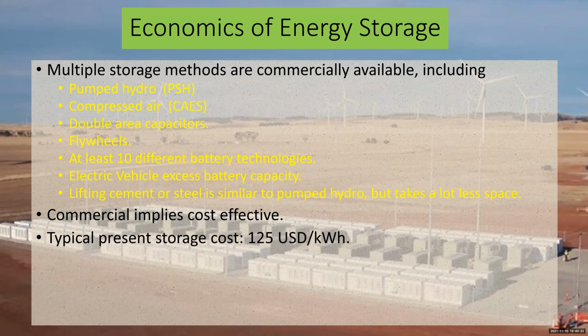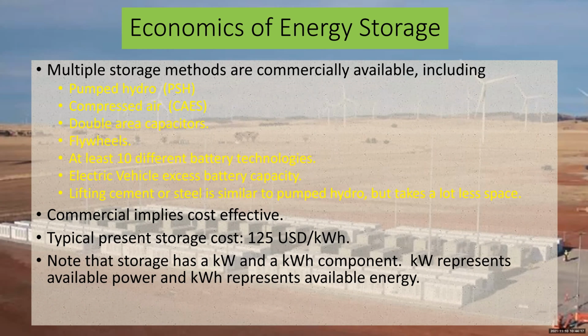Right now, storage is costing around $125 US per kilowatt hour. We learned from Orlando Utilities that this is for installation, but for every kilowatt hour you store, you can do that every day, in and out. So if you've got a 30 megawatt hour storage facility, you can fill it up and empty it every single day, amortizing the cost of those megawatt hours over the life of the system. According to numbers presented yesterday by the Orlando Utilities Commission, that added up to 0.7 cents per kilowatt hour of storage—for stabilizing electricity that utilities are now making for about 3 cents a kilowatt hour. So it's out there, it's happening, and that's why: it's cost-effective, it's commercially sensible.